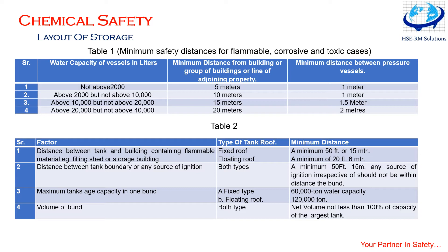Let us discuss bunds. In general, bunds are provided for atmospheric storage tanks and for fully refrigerated storage tanks of liquefied gases. Bunds are generally not recommended for pressurized and semi-refrigerated storage of liquefied gas. The purpose of a bund is to retain liquid so that it can be dealt with in a controlled manner. Atmospheric storage tanks are generally provided with full bunds. If there is more than one tank inside the bund, the capacity should be that of the largest tank, after allowing for displacement due to the other tanks.